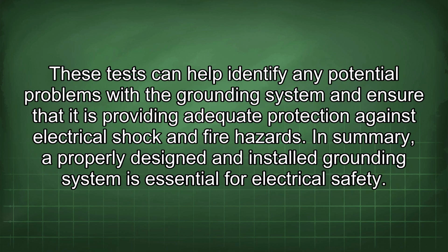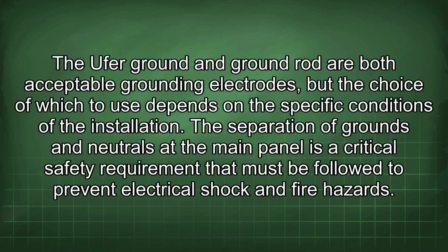These tests can help identify any potential problems with the grounding system and ensure that it is providing adequate protection against electrical shock and fire hazards. In summary, a properly designed and installed grounding system is essential for electrical safety. The Ufer ground and ground rod are both acceptable grounding electrodes, but the choice of which to use depends on the specific conditions of the installation.